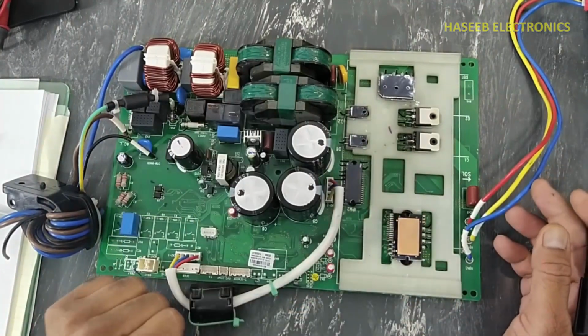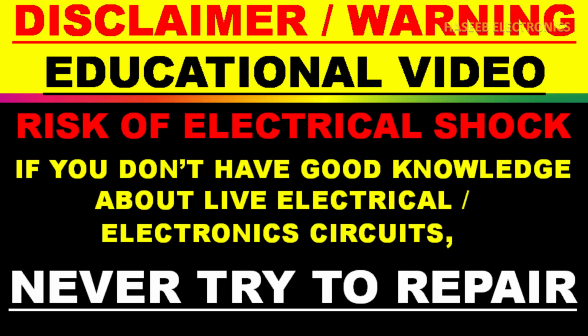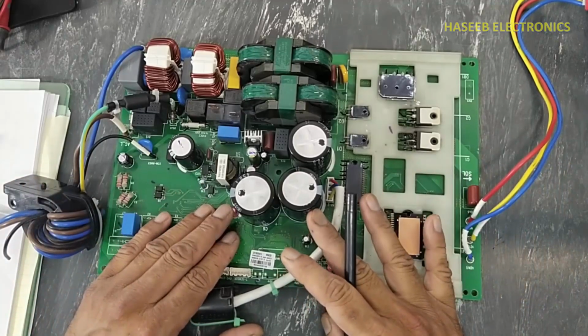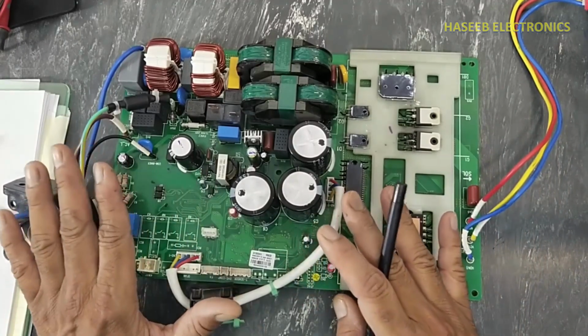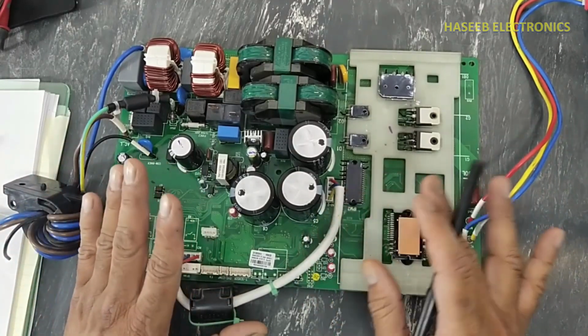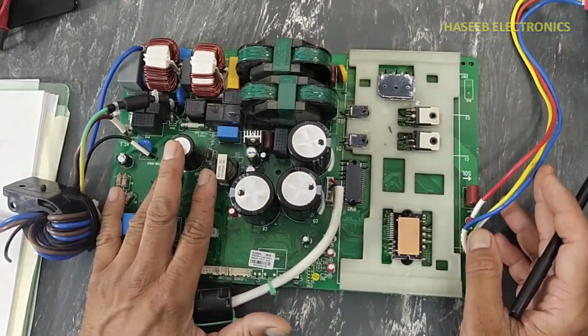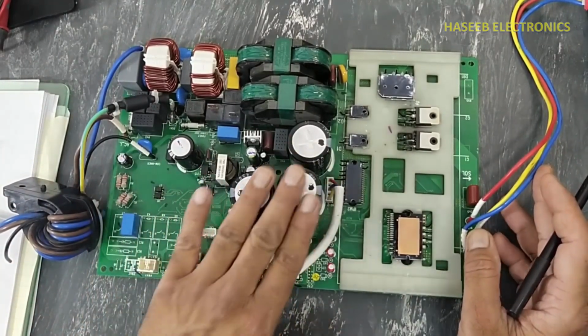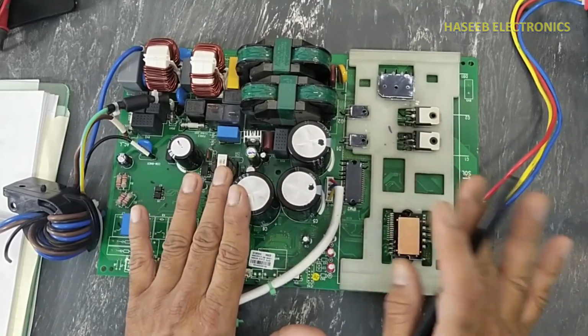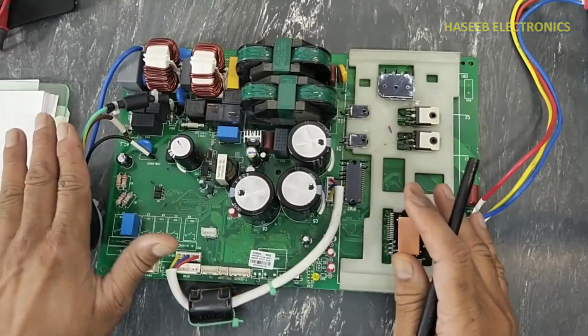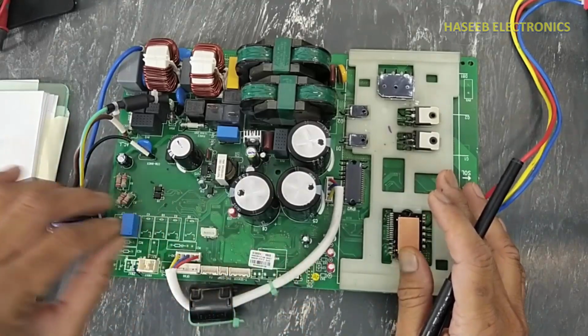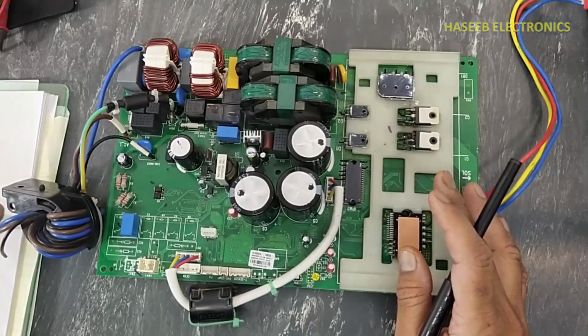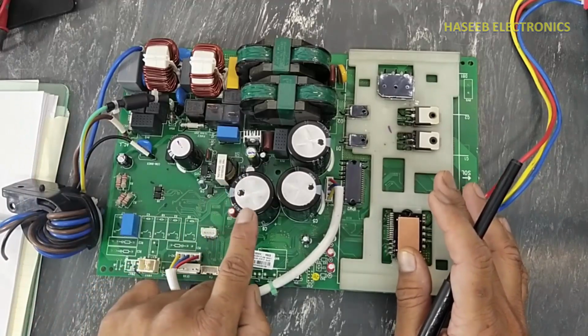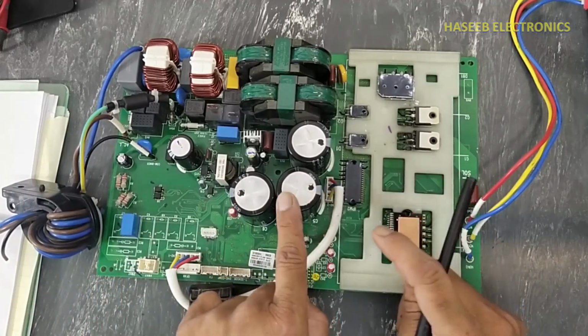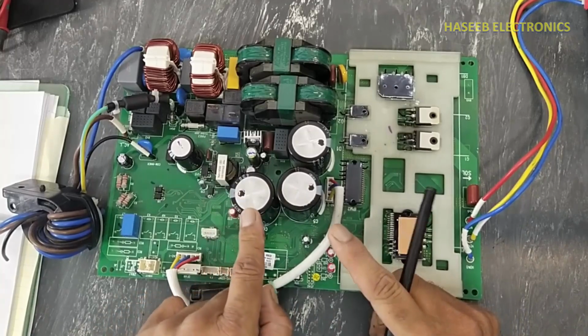Let's start to troubleshoot. If you don't have good practical experience in power electronics, never try to repair, because it has non-isolated live electrical voltage. When we are working on this board, first thing, never touch any component when power is applied, and when we are touching this board, remove power. After removing power, always verify voltage on these capacitors. If there is voltage, discharge it properly.